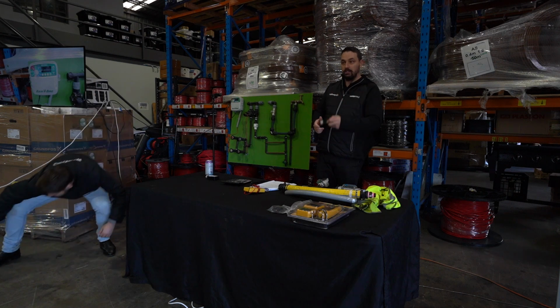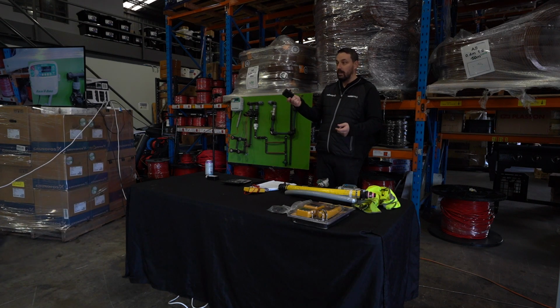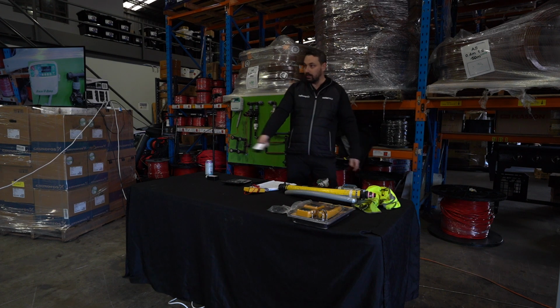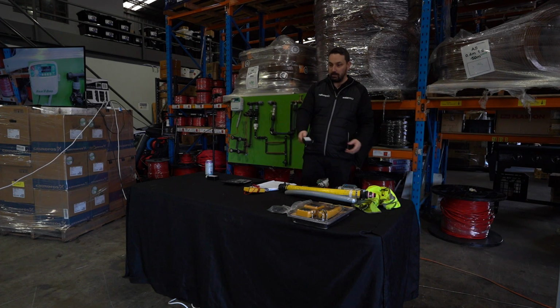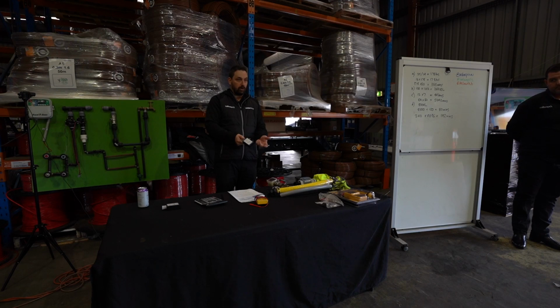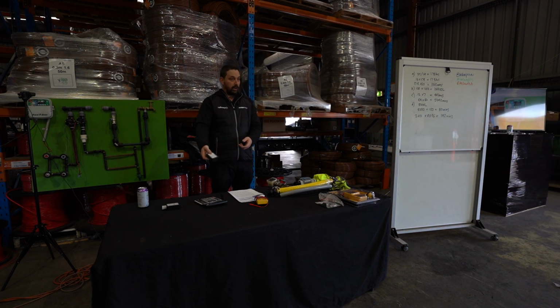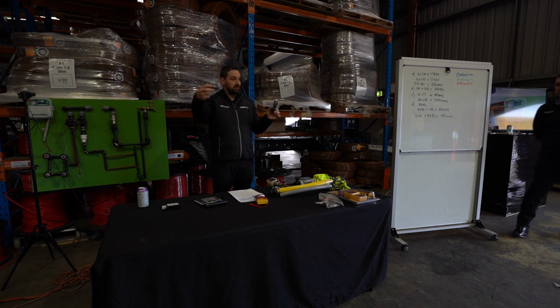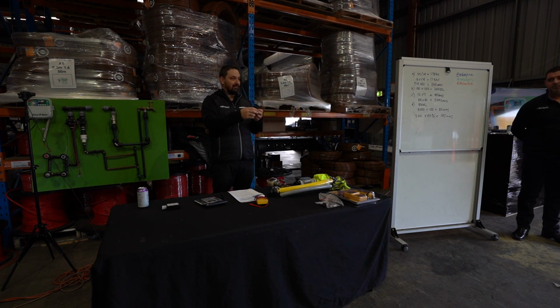The idea behind that is if you can't find a valve in the system, you can turn that valve on from the controller, walk around where you think it might be, and you'll hear it scream at you, an audio side of things, and you know that there's a coil down there. You'll be able to actually find it because it might have a hydraulic problem or someone's isolated a valve or something's happening. You can find that coil. That works when you've got continuity or a connection to that unit, because there's got to be power going down there too.